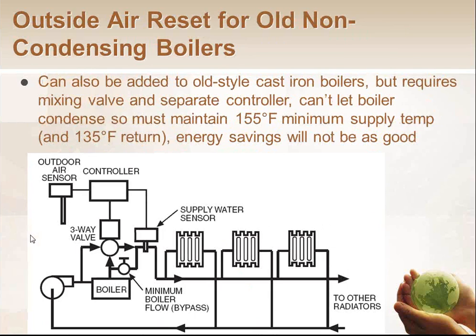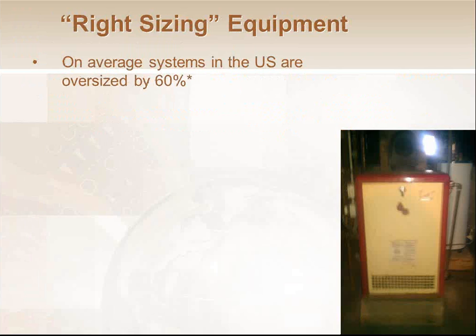Adding outside air reset controls to a non-condensing boiler can be a little bit tricky and costly. I've got to buy a controller, whereas with a condensing boiler, it's built into the existing controller, right? But here I've got to buy a separate controller and a sensor for outside air and a supply water sensor and wire all that stuff up, and possibly even a mixing valve to protect the boiler so I don't return very cold water. And now it's going to cost me $1,000, $1,500, something like that. So if I've got a 5 million BTU boiler that's in good condition, it would make sense to pay to add these controls and save some energy, right? But if I have a 500,000 BTU boiler, buying $1,500 worth of controls probably isn't going to pay itself back. So I'd probably be better off upgrading my boiler plant. Kind of how that usually goes.